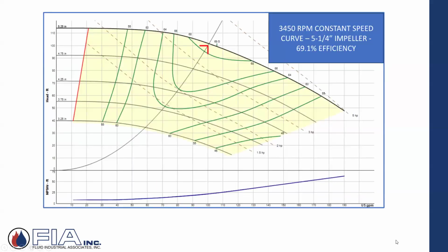And what I'm going to do here is highlight a pump curve that maybe got selected with some pump software that says, hey, 100 GPM at 100 feet of head. Here it is. A 3450 RPM constant speed pump is what I selected. These are pretty unusual conditions, 100 at 100, but it's just an example to work with.